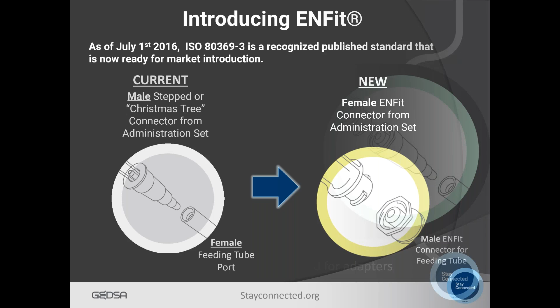We also know that tubes are in place sometimes months, if not years, and so we know it's essential to have what we call a transition connector, which allows for backwards compatibility. In this slide, you'll see from the upper left portion the ENFit female coming from the giving set with the transition connector, that's the male part, that allows for a step connector that could then go into a traditional feeding tube or a legacy feeding tube. This is going to be in use for a period of time until we know that the feeding tubes have collectively been transitioned over to an ENFit connector.